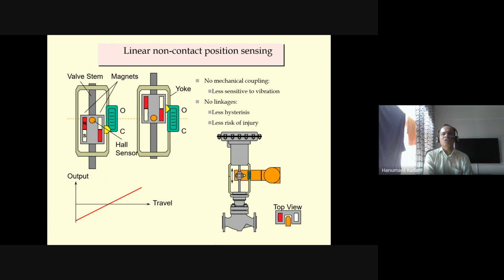When we switch to linear non-contact positioner sensing, how does it work? You can see here, this is the valve stem. You can see a scale on this yoke, open and close position, and this is a pointer moving up and down, right? So north and south pole magnet here. Here also, this is north and this is south. And there is one sensor on this plate called a Hall sensor. So now the valve is in closed position, and here the valve is in open position. So you can see here no mechanical coupling, less sensitive, no linkages. Like this, it is installed.